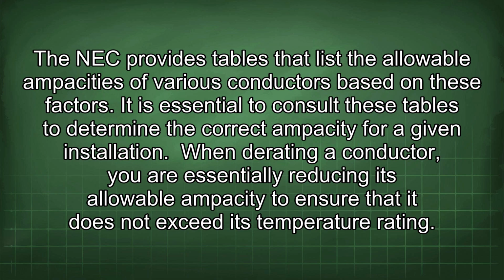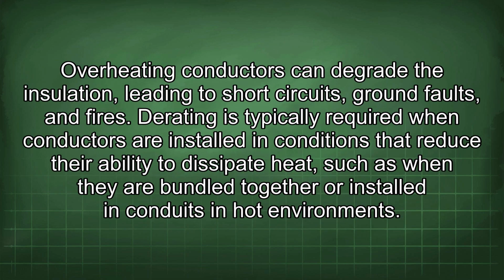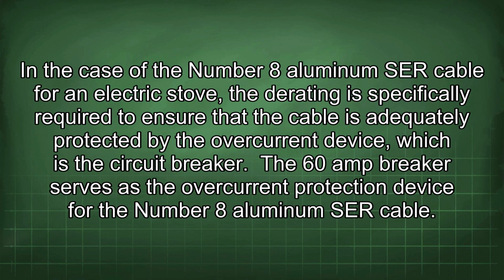When derating a conductor, you are essentially reducing its allowable ampacity to ensure that it does not exceed its temperature rating. Overheating conductors can degrade the insulation, leading to short circuits, ground faults, and fires. Derating is typically required when conductors are installed in conditions that reduce their ability to dissipate heat, such as when they are bundled together or installed in conduits in hot environments. In the case of the number 8 aluminum SER cable for an electric stove, the derating is specifically required to ensure that the cable is adequately protected by the overcurrent device, which is the circuit breaker.